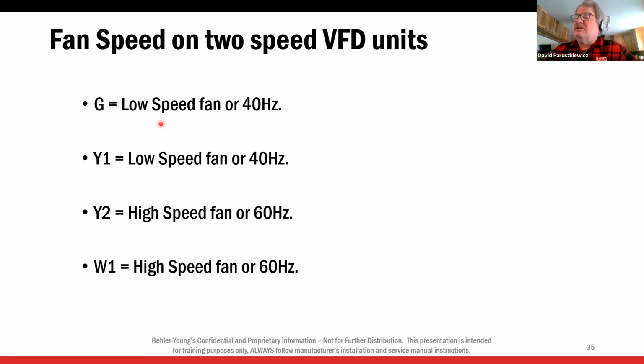So G, circulation fan, and first stage cooling, we're going to send 40 hertz to the blower. It should run at about 66% speed. Y2 or W1, we're going to full speed, 60 hertz. That's all that drive is doing, all right?